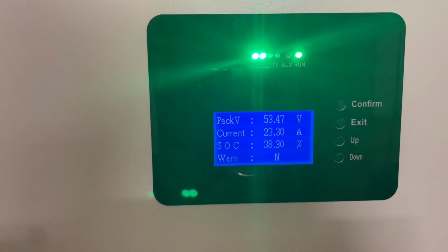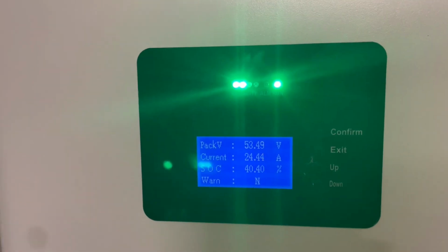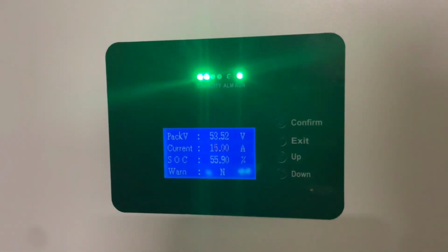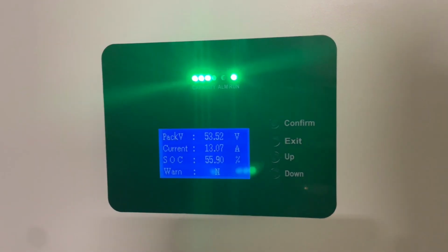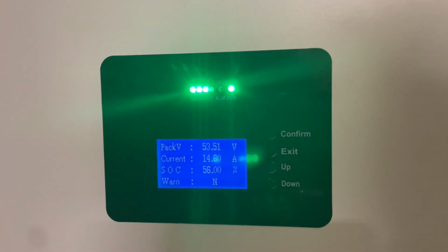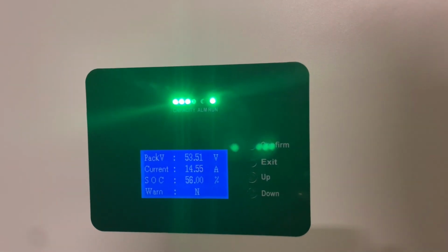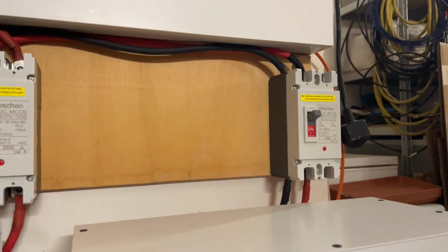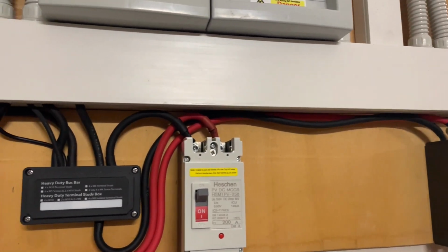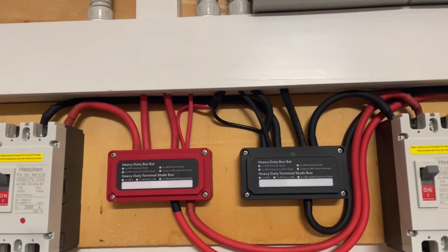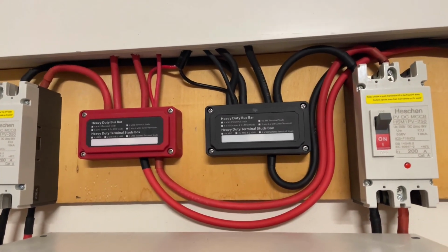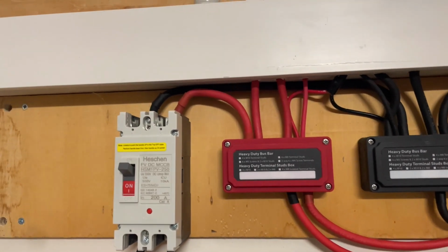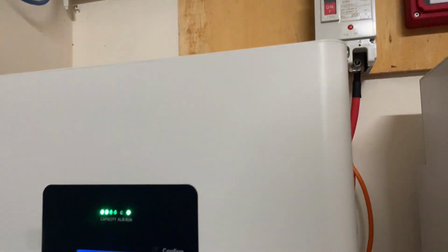That's the original primary battery bank, that's the original secondary battery bank, and that's the new third battery bank. As you can see, the state of charge is quite significantly higher on the third battery bank compared to the secondary and the primary. Now if you look at the cable lengths, the primary has got the longest cable run from the bus bars. The secondary has got a slightly longer cable run than the cable run from the bus bars to the third battery bank.